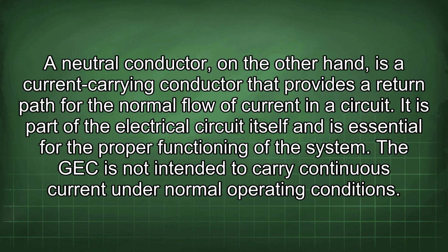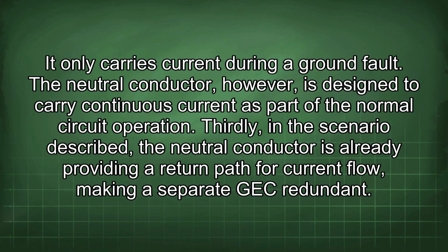A neutral conductor, on the other hand, is a current-carrying conductor that provides a return path for the normal flow of current in a circuit. It is part of the electrical circuit itself and is essential for the proper functioning of the system. The GEC is not intended to carry continuous current under normal operating conditions. It only carries current during a ground fault. The neutral conductor, however, is designed to carry continuous current as part of the normal circuit operation.